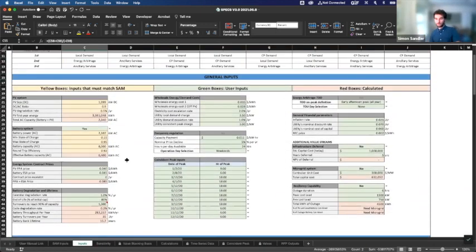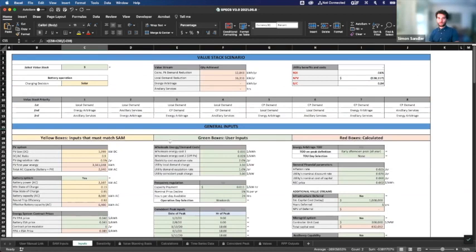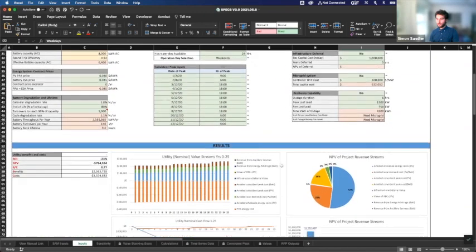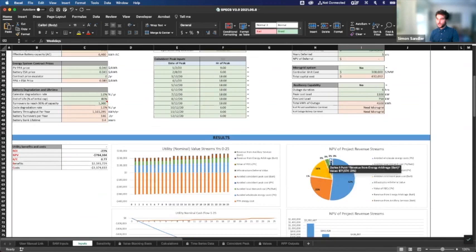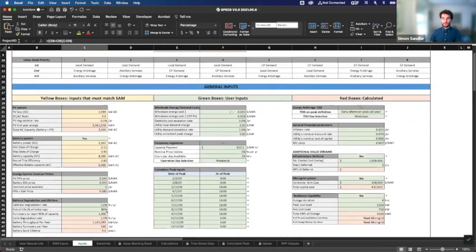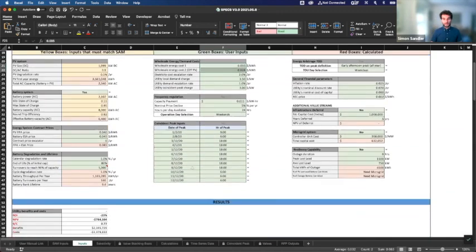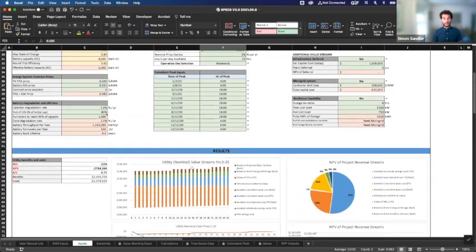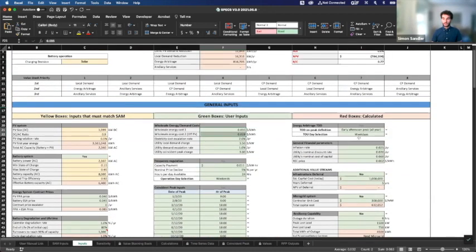What was just walked through was a basic preliminary analysis. There are lots of potential opportunities for future analysis. For example, what if time of use became a thing? If you come up and say energy arbitrage is being used on weekdays, you'll immediately see a change — there's now revenue from energy arbitrage at 3%. However, notice the ROI actually went down. That's because under this situation with battery degradation and the value difference between off-peak and on-peak, it actually costs more to operate the battery for this purpose than the gain. So you can toggle features on and off to learn from the analysis.